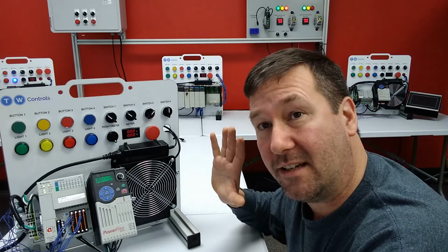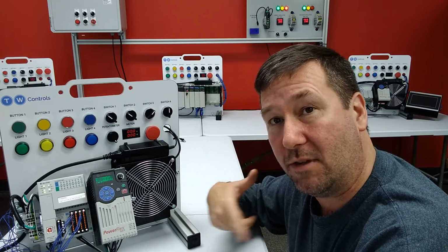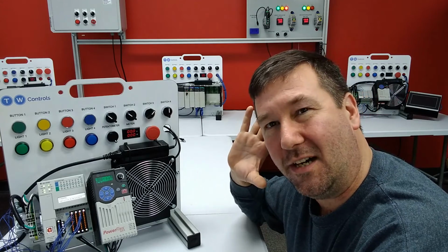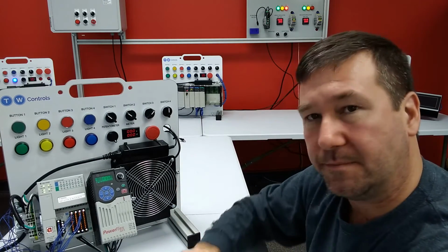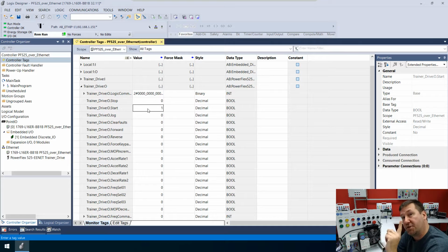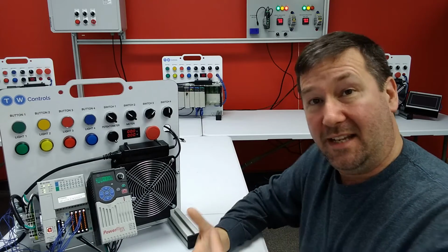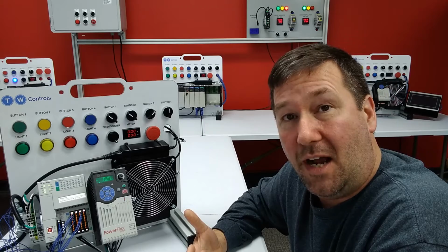And your drive probably sounds like mine. It's got an annoying fan that's blowing on this mic really bad. We hear a little bit of hum, but we're not moving. Also, let's just put a 0 into that start. And we notice we still have the hum and this annoying fan. Well, we're going to have to put a 1 in this stop bit. And you're going to hear that little click. The hum went away, and in a minute, our fan's going to turn off. And I'm going to go ahead and put a 0 in that stop bit. So it is working. It is controlling the drive.